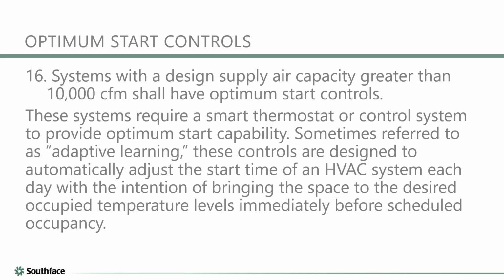One way we typically look at this is like the difference between warming the building back up in January on Monday morning versus warming the building up in January on Tuesday morning. Monday morning, the building's been colder and unoccupied for a longer period of time, so maybe the system learns that it needs to come on at 7 a.m. in order to get to your desired thermostat settings by 9 a.m. Versus Tuesday morning, you don't have as much downtime, and you're able to bring the system on at 8 a.m. to hit your desired set points when necessary. So that's how these optimum start smart controls function in a building.